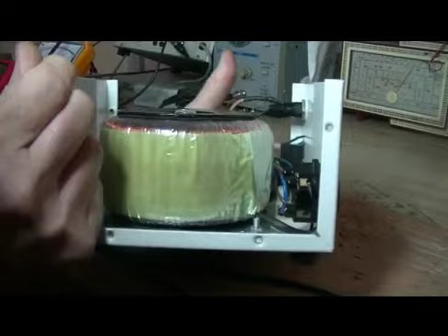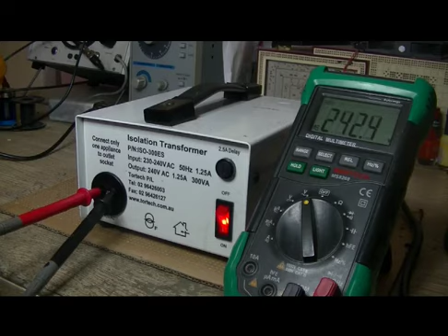Before I get onto the safety issues, I just wanted to see what this is outputting. Is it exactly 240 volts? I doubt it's exactly that. I plugged it into my power board to see what we're going to get out of it. Switching it on, I've got 242 volts coming out. Not bad. That tells me it's not exactly a one-to-one winding, but hey, close enough. Cool.